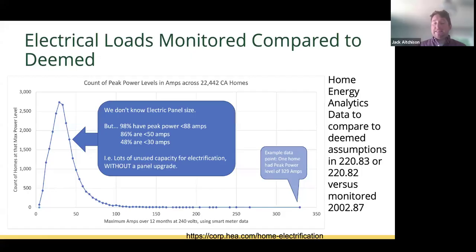What we found is that this significantly overestimates the actual peak amp draw. The electrical code actually allows you to use monitoring data rather than that calculated required capacity to determine your existing usage, and we can see that here.